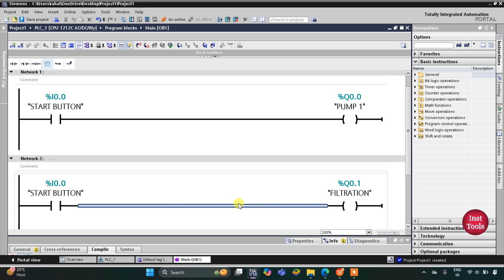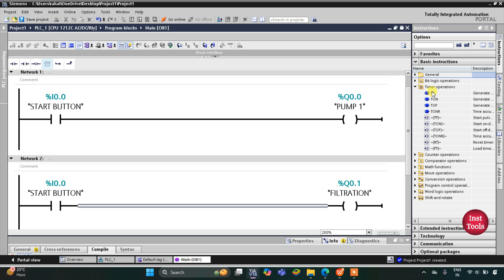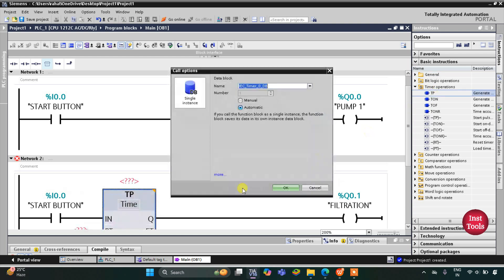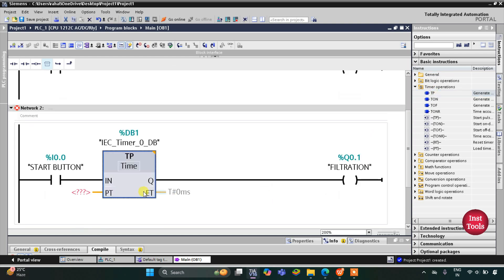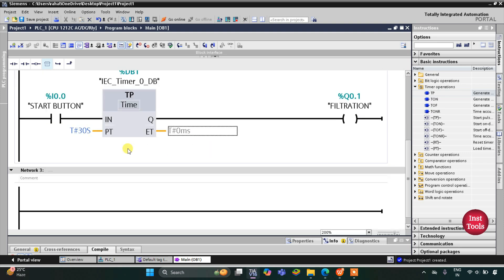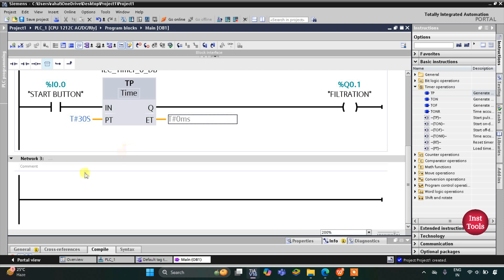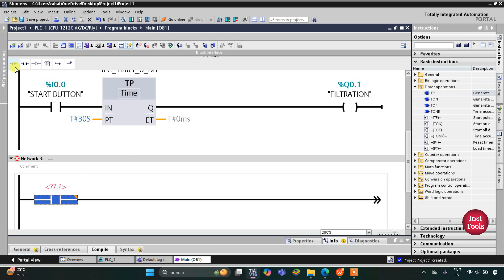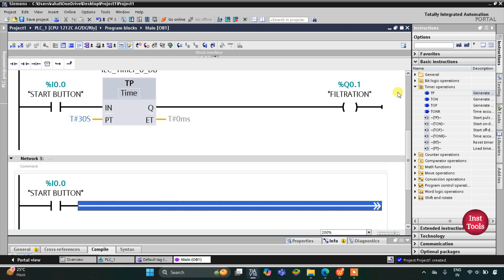This coil will be for filtration. The process of filtration will go on for 30 seconds. For that I will use a timer operation — a TP (pulse timer). The preset value for this timer will be 30 seconds because the filtration will go on for 30 seconds.